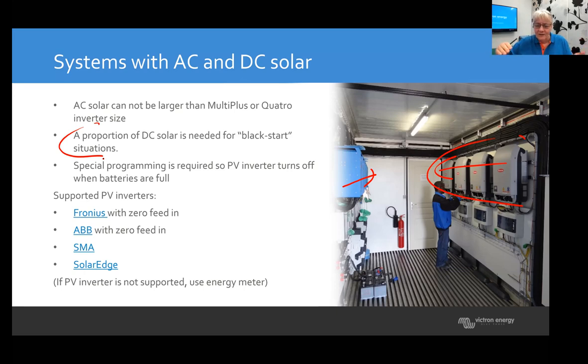So it wants to work, but because the batteries are empty, there's no grid for the PV inverter to latch onto. That's the main reason why, if you have DC in the system and the sun comes up in the morning, DC will always work. DC will charge the battery up again, and once the battery is high enough, the inverter will charge again, and this happens automatically. Then it starts making grid, and then the big grid feed inverters turn on. So it's important to always have a proportion of DC solar.